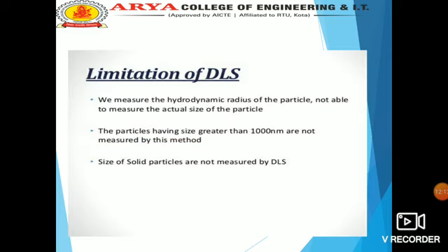And the limitations of DLS: we measure the hydrodynamic radius of the particles or molecules, not the actual size of the particles and molecules. Particles having a size greater than 1000 nanometers are not measured by this DLS method. Size of solid particles is not measured by DLS.